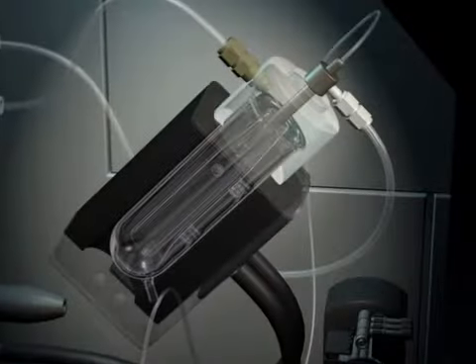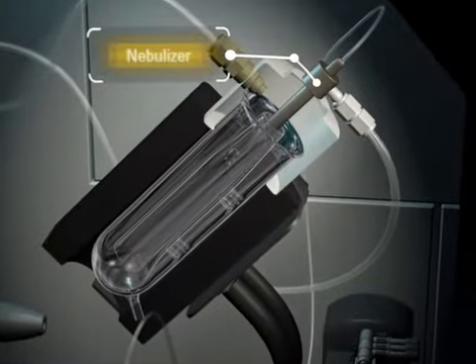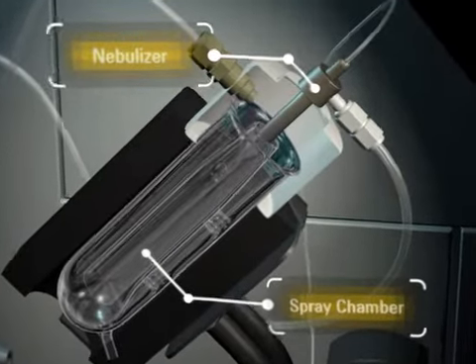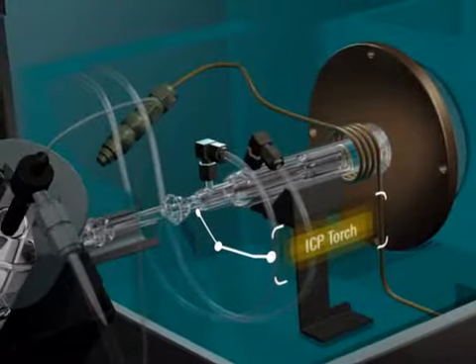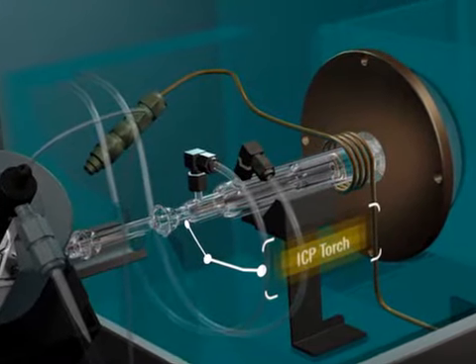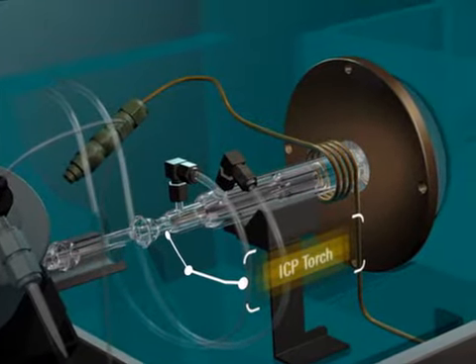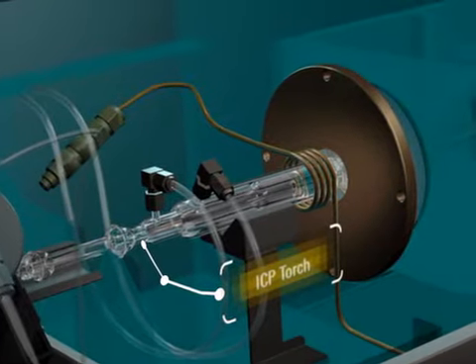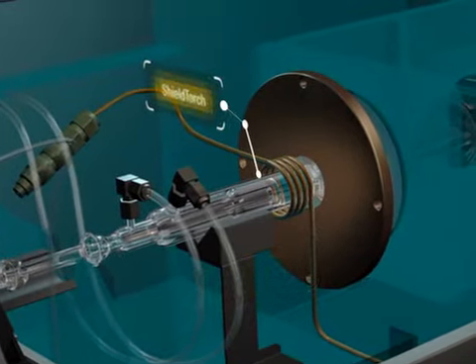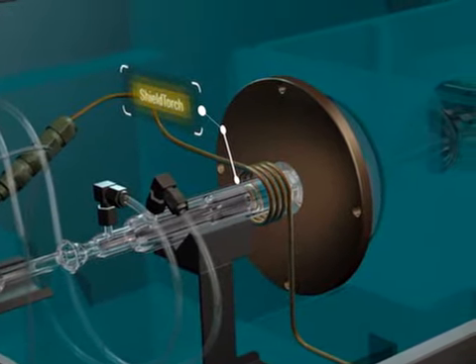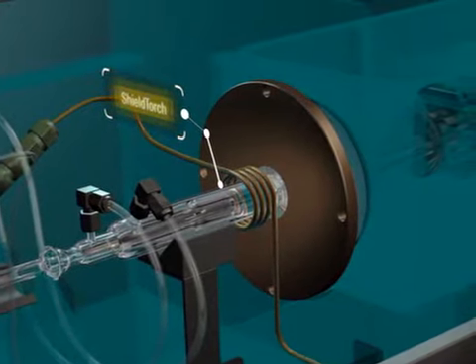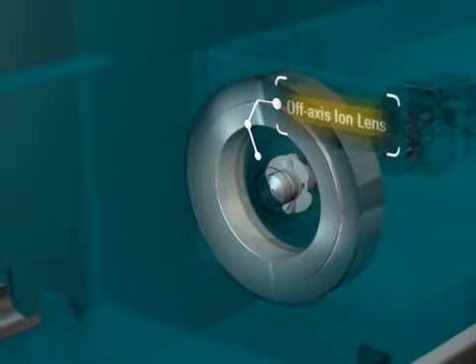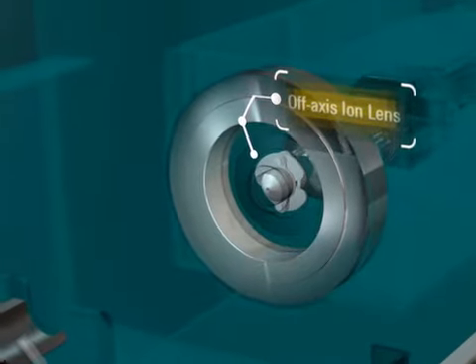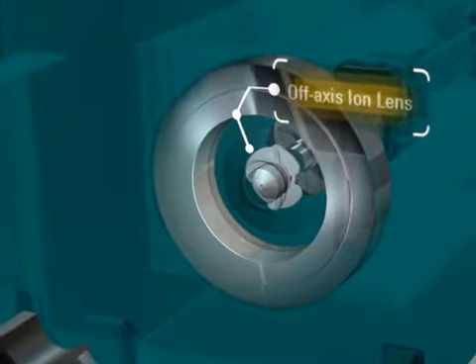The sample introduction system consists of a nebulizer, spray chamber, and ICP torch. Ion generation takes place in a high-temperature 27 MHz plasma. Agilent's unique shield torch system reduces ion energy spread, allowing optimum ion focusing and increased sensitivity. The off-axis ion lens system ensures high ion transmission across the entire mass range, plus low background noise.